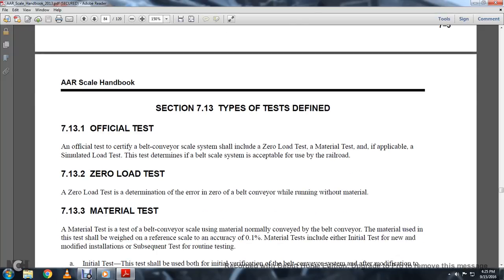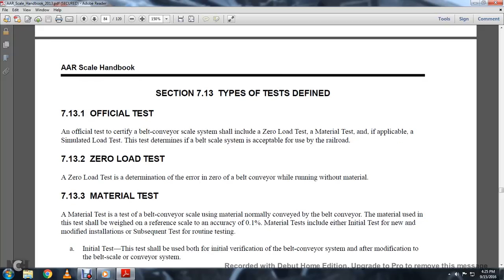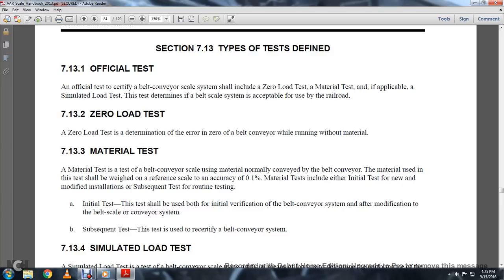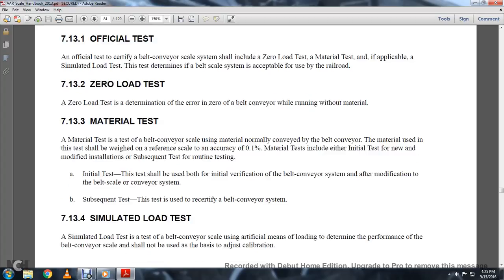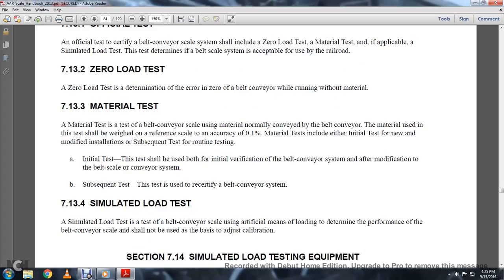Section 713-2, Zero-Loaded Test. The zero-loaded test determines the zero error; the belt conveyor will run without material. Section 713-3, Material Tests. The material test uses the belt conveyor scale with the material normally conveyed by the belt conveyor. The reference scale used shall have an accuracy of 0.1%. Material tests include initial testing of new or modified installations, subsequent tests, and routine testing.